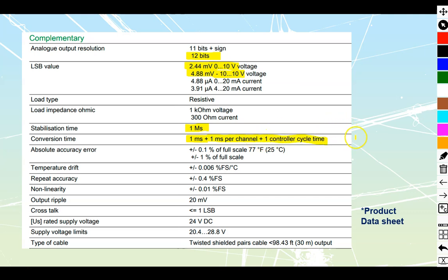In other words, the amount of time it takes for us to make a change in our program and then see it affected in the real world is going to be the milliseconds of the actual change, the milliseconds for other channels to do a scan, plus whatever your cycle time is. So it's really dependent mostly upon how streamlined your code is and how fast your CPU is. Different CPUs are going to have different controller cycle times as a default.